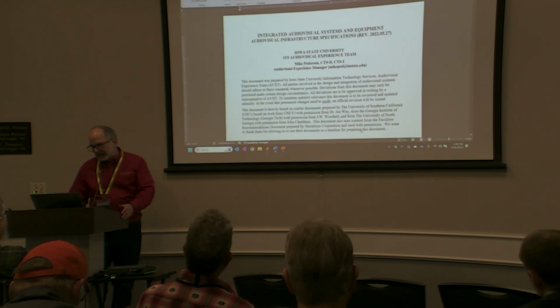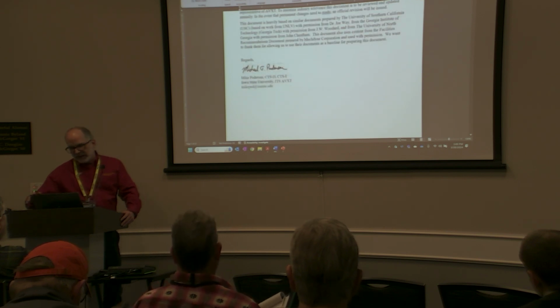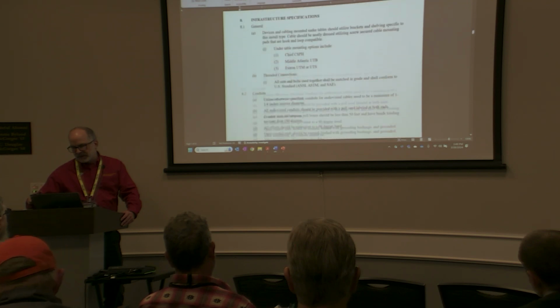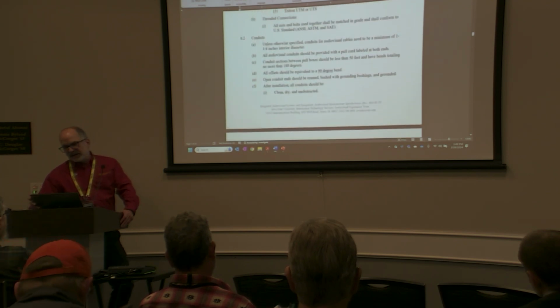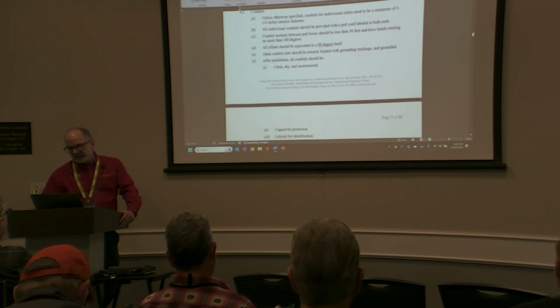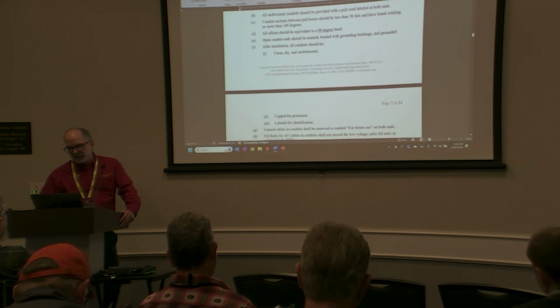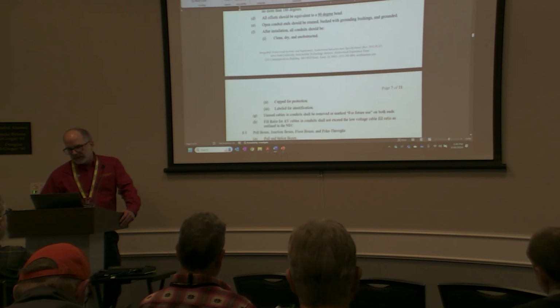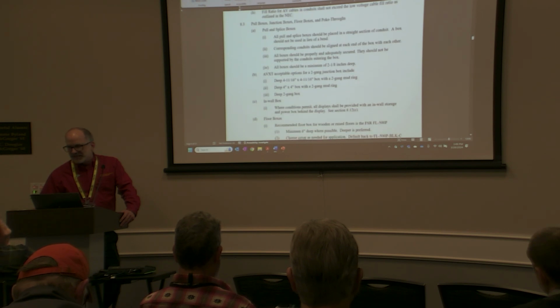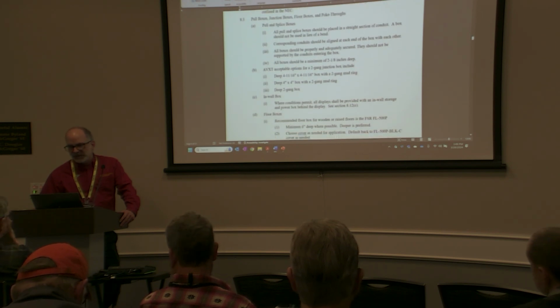We also have this in a text form that's not in that master format, like we have laid out here. But again, this talks about—cut through here—conduits, unless otherwise specified, shall be 1.25 inch, shall be provided with a pull string already inside, labeled at both ends. Conduit sections between pull boxes should be less than 50 feet and have bends totaling no more than 180 degrees. So again, a lot of dry details, but also things that are going to make your life better down the road, as you go.